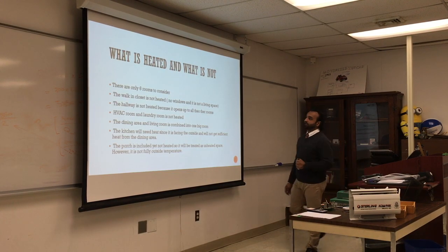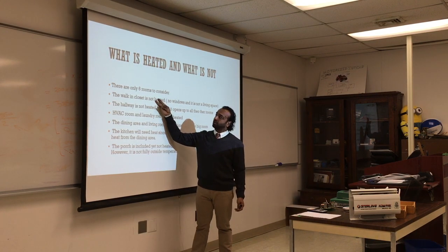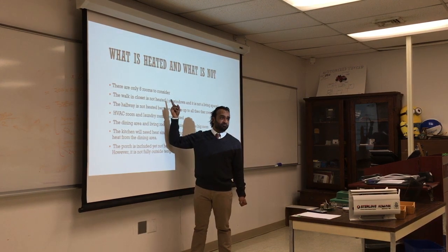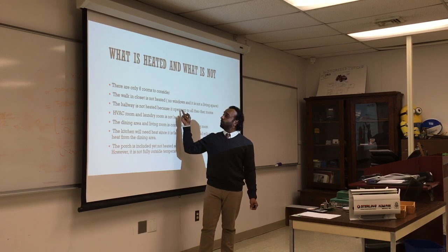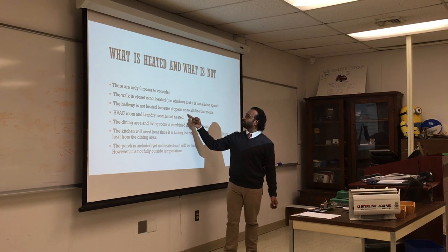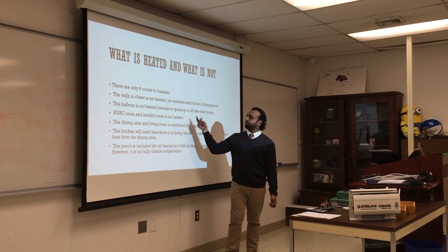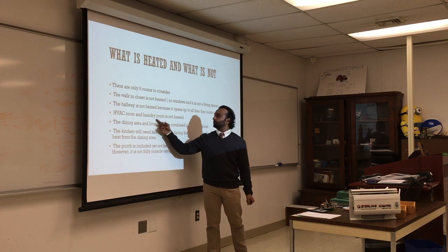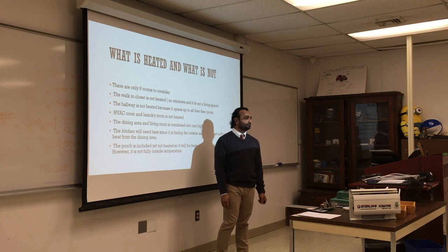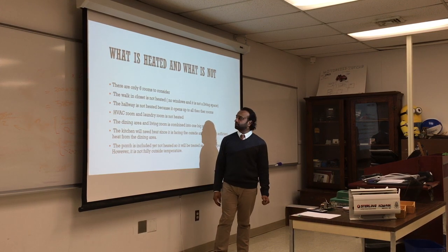So again, what is heated and what is not? For this house, there are only 6 rooms to consider, not a lot. The walk-in closets are not heated. They're too small, and you shouldn't heat a walk-in closet. The hallway is not heated because it's open to all the other rooms, so whatever heat comes from the rooms is going to go to the hallway. No need for that. The HVAC room and laundry room are not heated. There's a lot of heat from the washer and dryer, so no need for that.